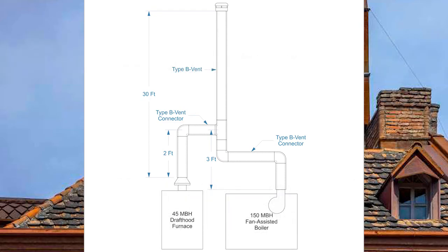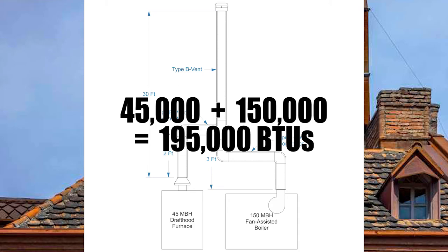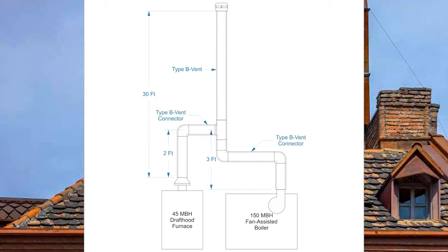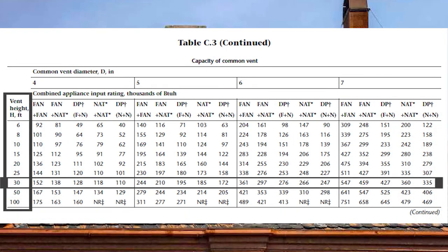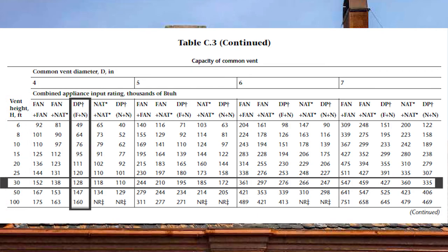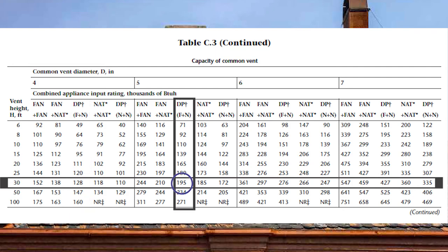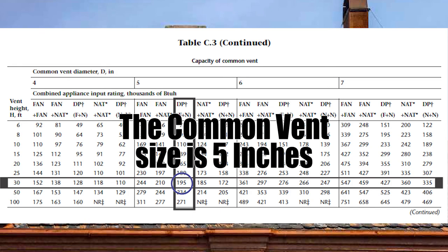Time to size the common vent. Adding up the total BTU load: 45,000 plus 150,000 is 195,000 BTUs. Turning to page 200 to size the common vent capacity, I come down on the left to 30 feet and across to DP F plus N — fan assisted plus draft hood equipped appliance. Four inch is good to 128,000 BTUs, which is not enough. Five inch is good to 195,000 BTUs — exactly what I need. I will select a five-inch common vent.